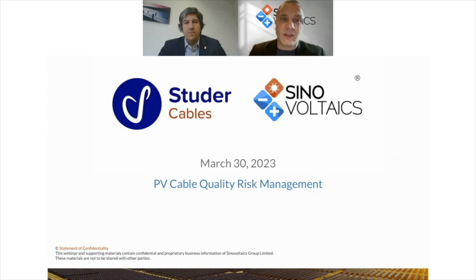So our PV and battery energy storage quality management or quality risk management services and decade-long expertise go beyond the big ticket equipment like modules, inverters, and containerized BESS systems, but also to the critical balance of systems or BOS components such as PV cables. And today, drawing basically from our team's extensive track record in PV cable quality assurance and also technical advice to manufacturers regarding quality management, system setup and testing procedure development, in this introductory part I will speak about the key quality requirements for PV cables, common PV cable quality tests, and quality risks revealed by these tests basically.